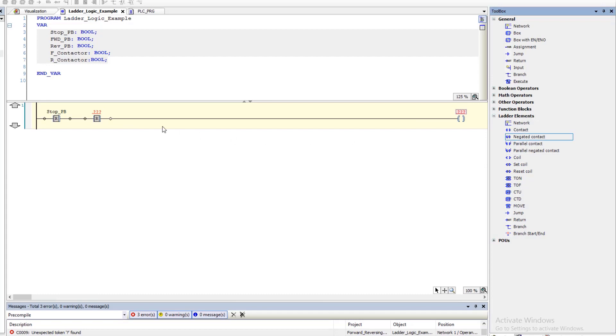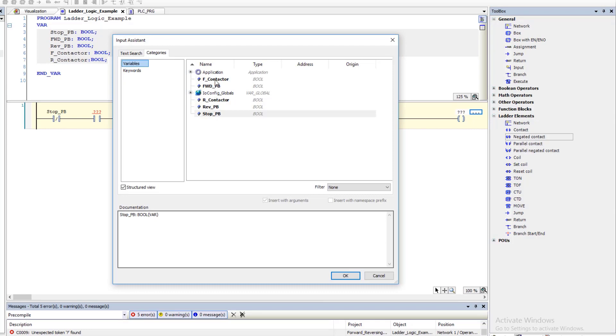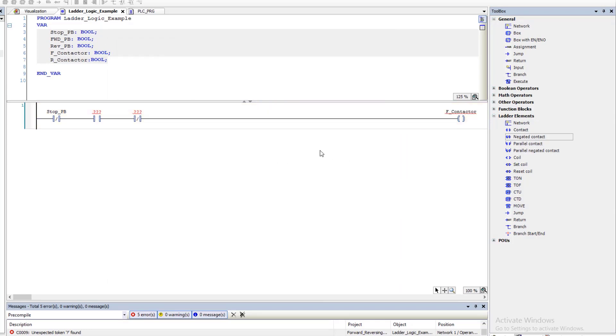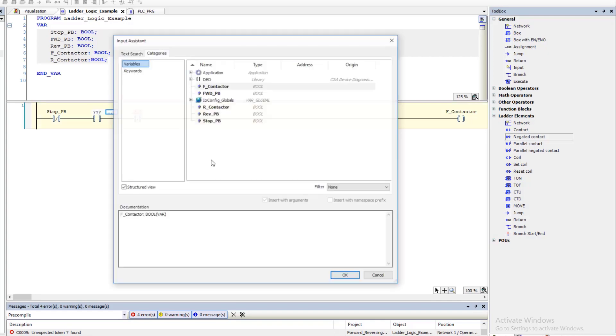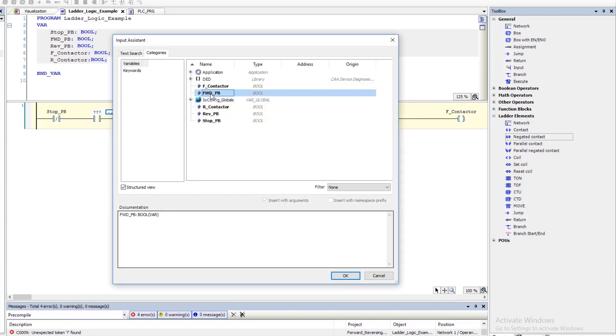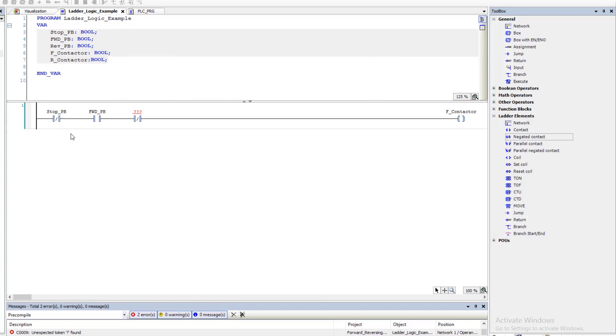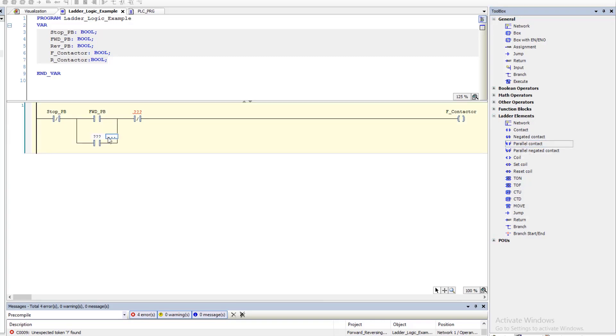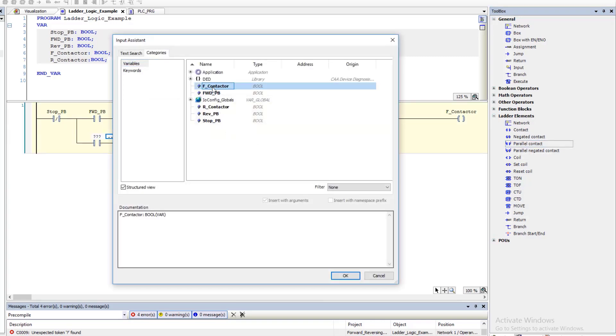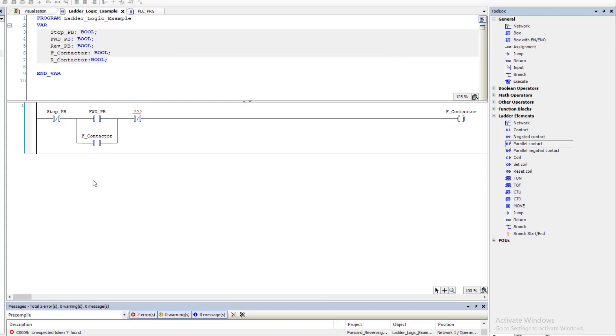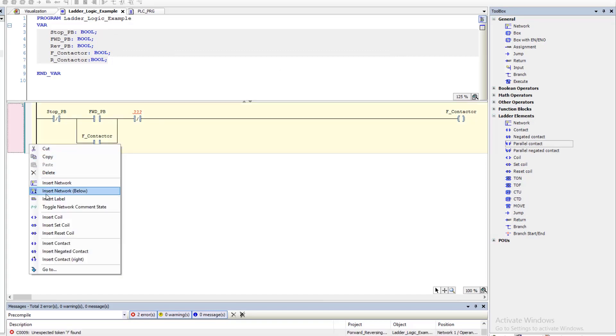We're going to add in another negated contact — this is going to be the forward contact. This is the actual forward push button. Now we want to have this seal in like a seal-in circuit, so let's go ahead and add a parallel circuit here. The coil is going to be the forward contactor.